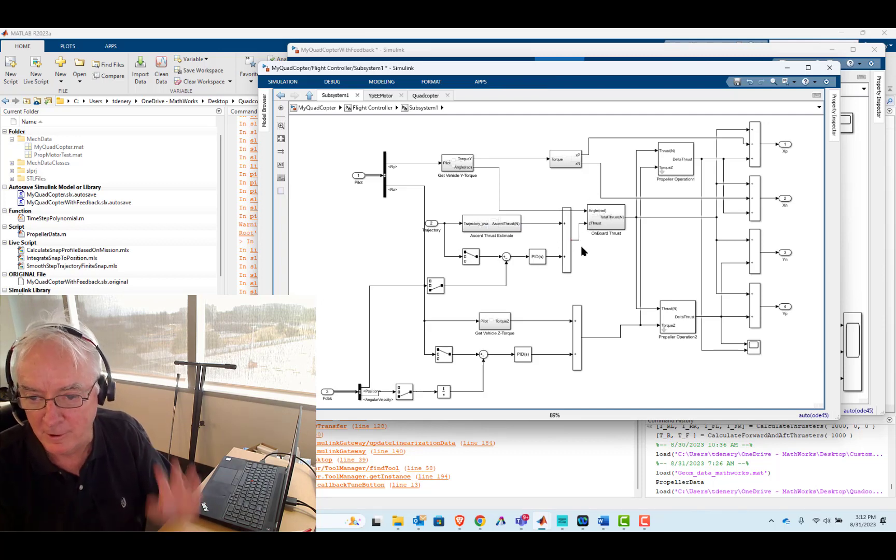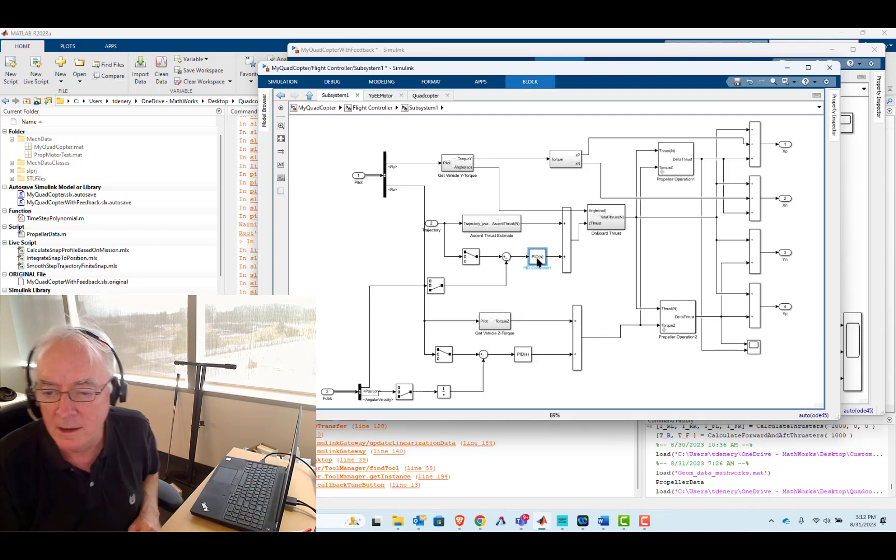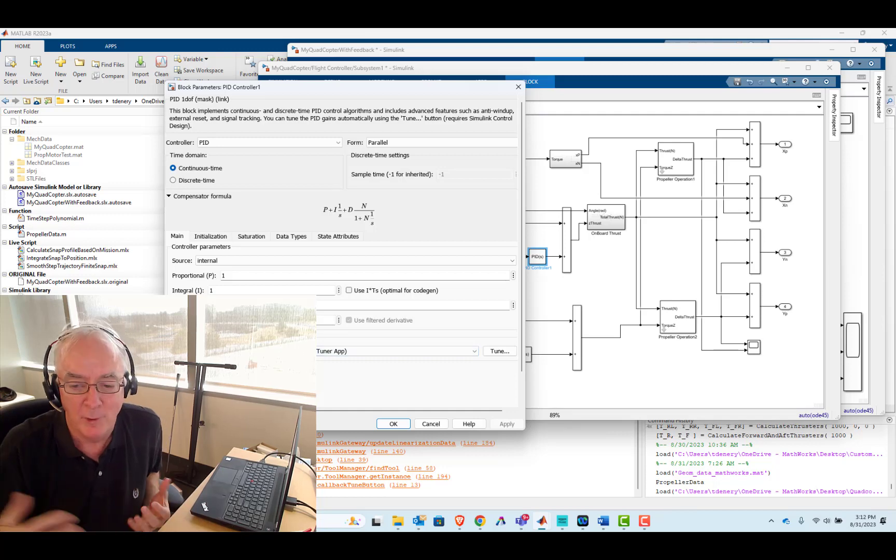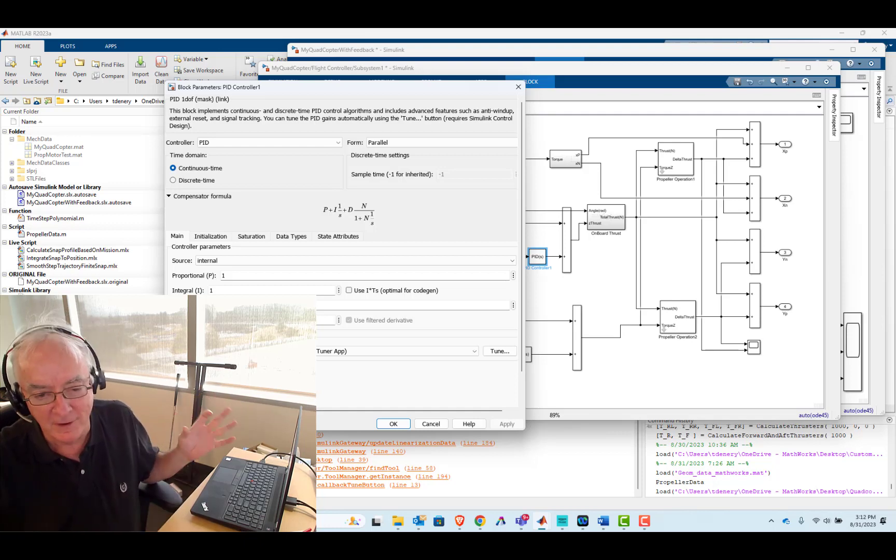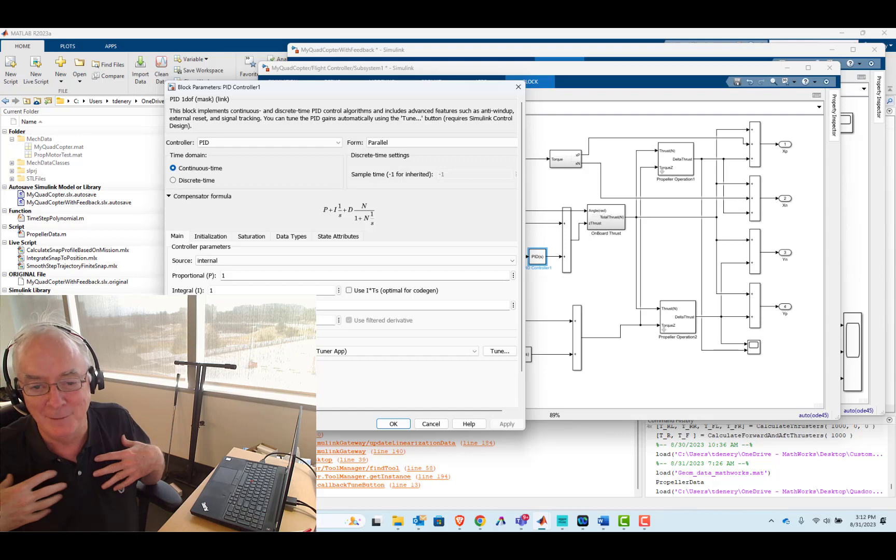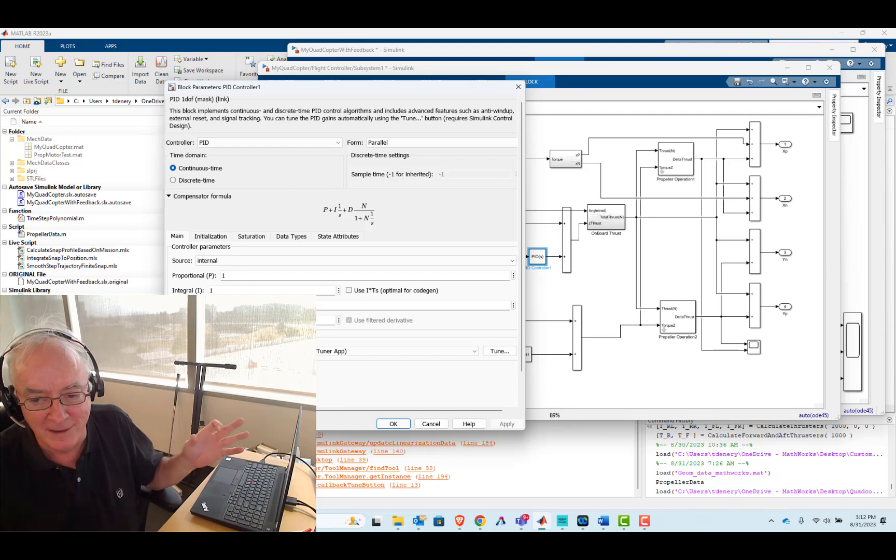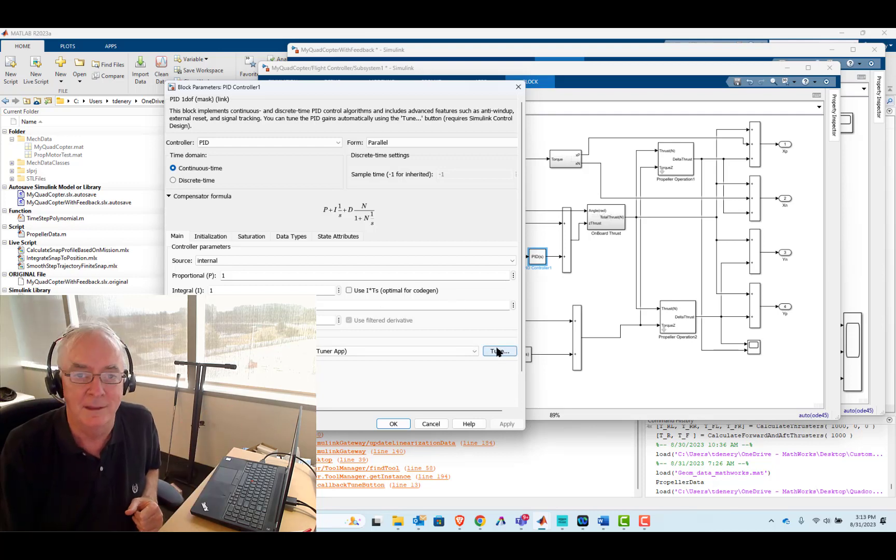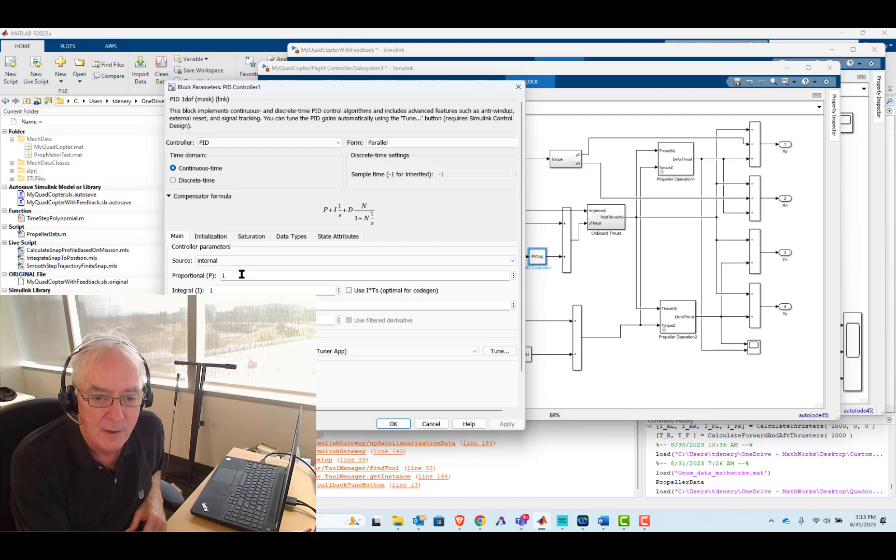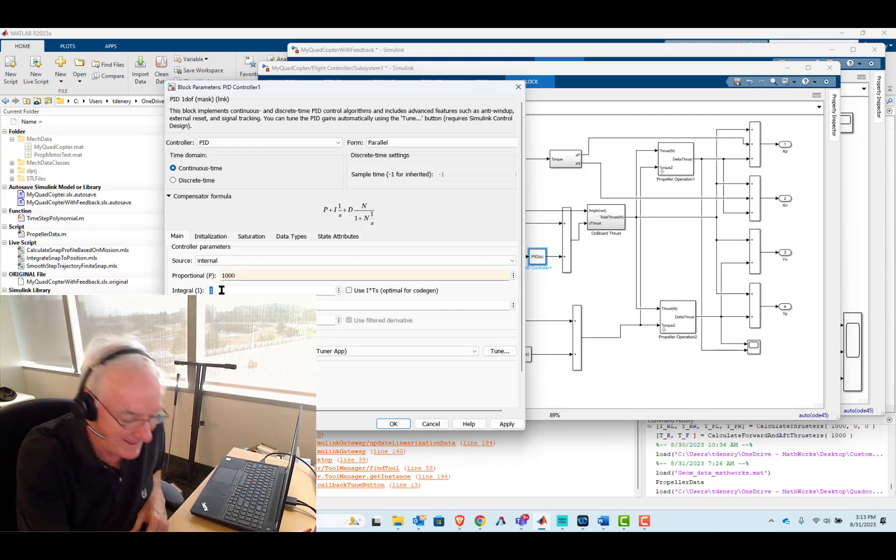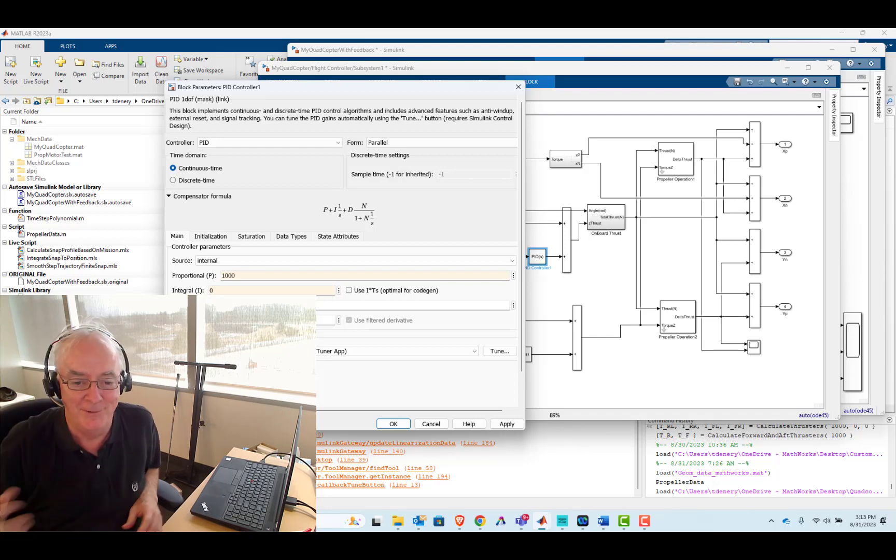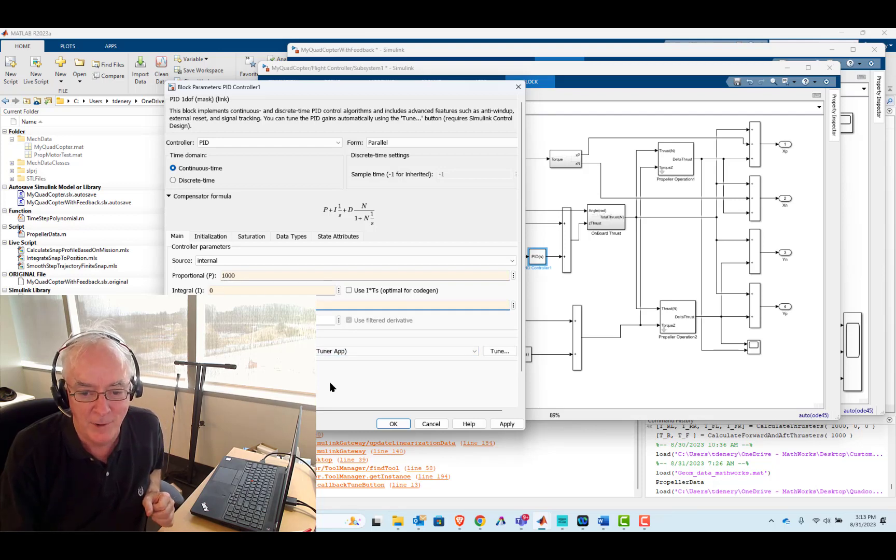And I don't like all these lines crossing, so I'll clean this up soon. And just comment, as I work through this, we're adding more and more feedback approaches. We're using something to handle something messy. And it is amazing how well PIDs work at that. But as I brought some of these in, sometimes you find that PIDs can fight against each other, and certainly this tuning led to something that didn't work real well for me. But what I reasoned it to was, well, my requirements are simple. And that if it takes like five seconds for it to get the right Z adjustment because maybe the wind blew and pushed it up too far, I'm kind of okay with it. And so I just put in my own numbers and it ended up working out pretty well.